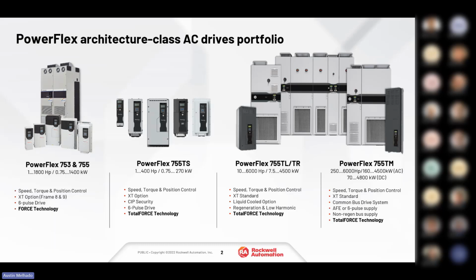Rockwell released this back in 2010, 2012, and it was the upgrade, or the next version rather, from the PowerFlex 700. Their general purpose drive came in as a 6-pulse drive in various horsepowers from 1 horsepower to 1800 horsepower. With the Force technology, just before COVID, Rockwell released the 755, the first version of the T family, which was the 755 TL and the TR and the TM actually.